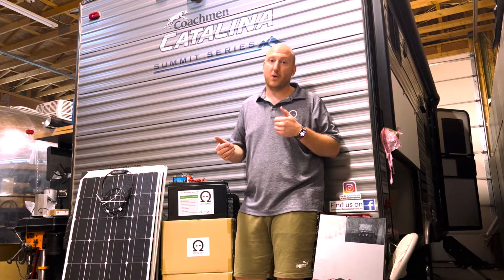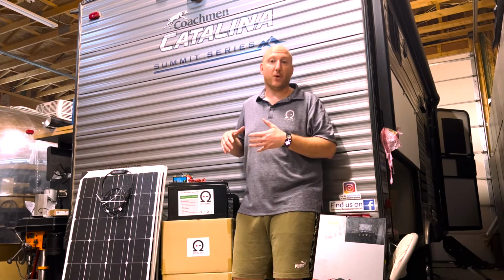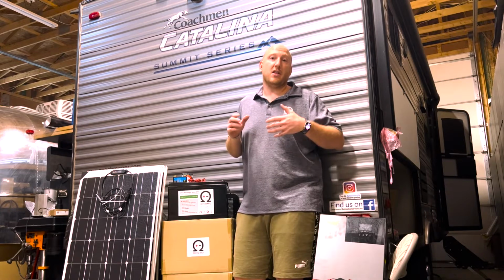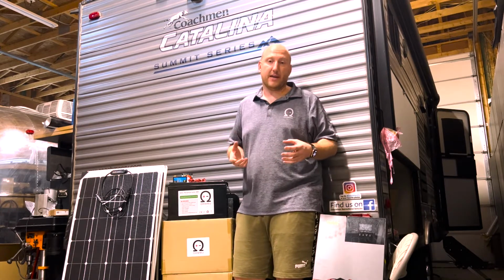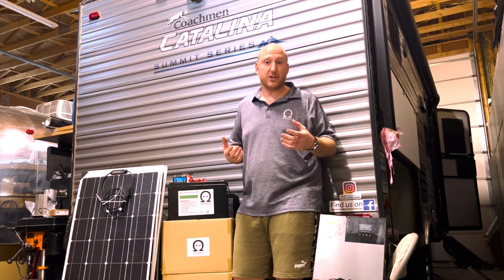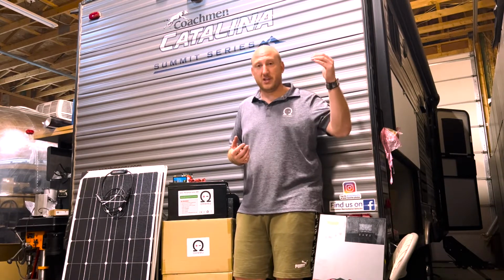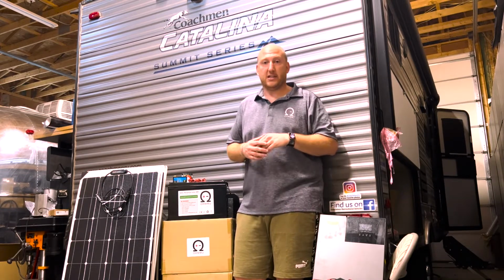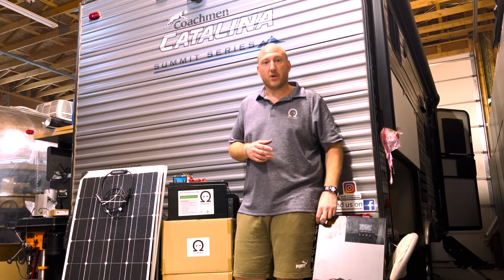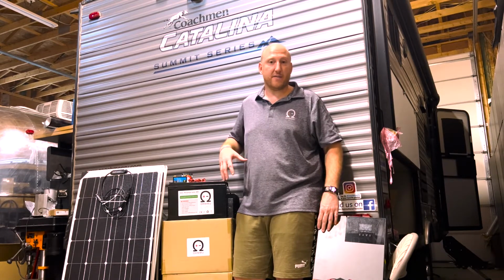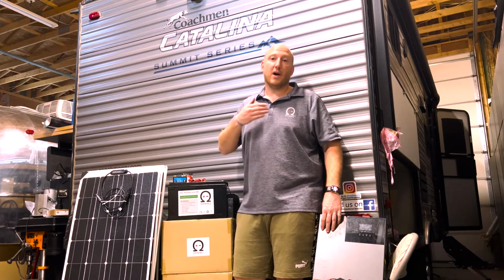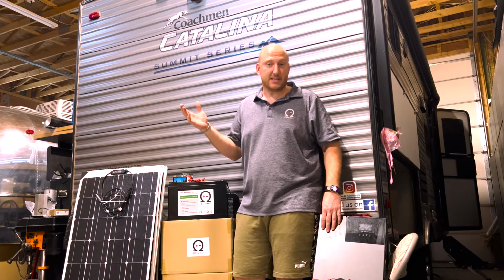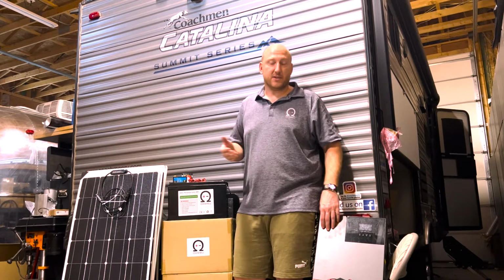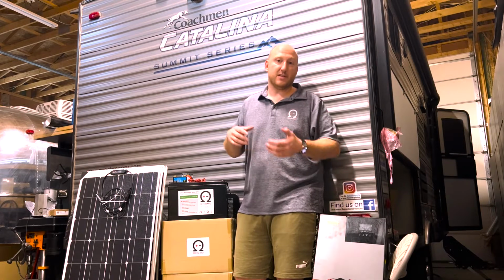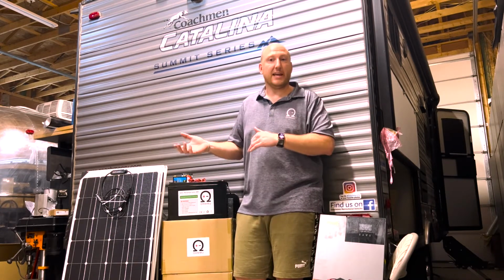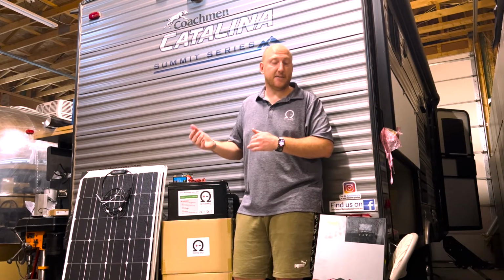So rather than a 12-volt system, this creates a 48-volt system. The reason that's beneficial, where you have the opportunity to do so, is that higher voltage equals higher efficiency. With things like running an inverter, where you have a significant amount of energy available and want to run it for hours or even days at a time, the efficiency makes a difference. The difference between an 85% conversion efficiency and a 92% conversion efficiency is significant.